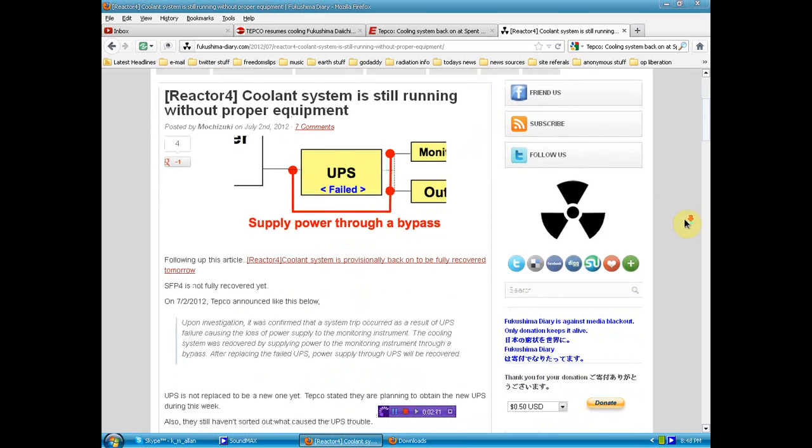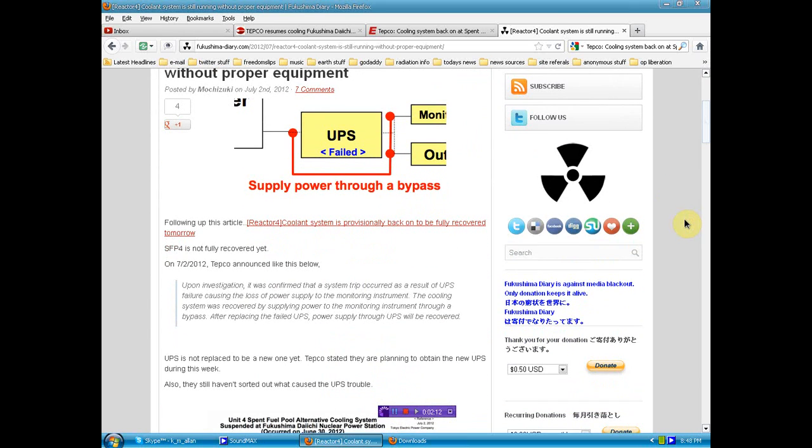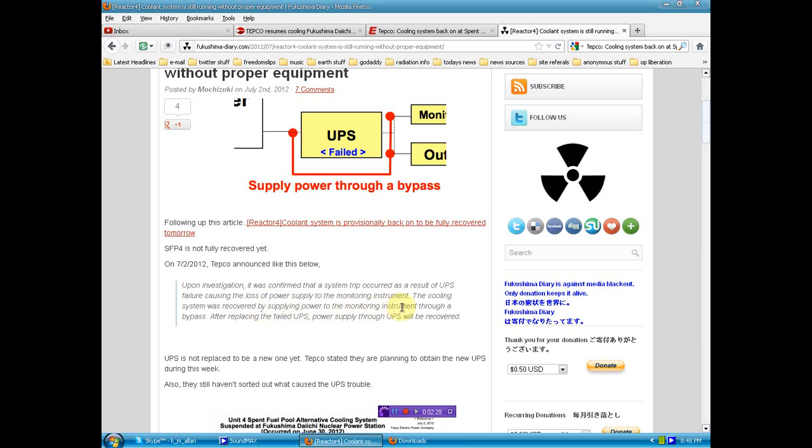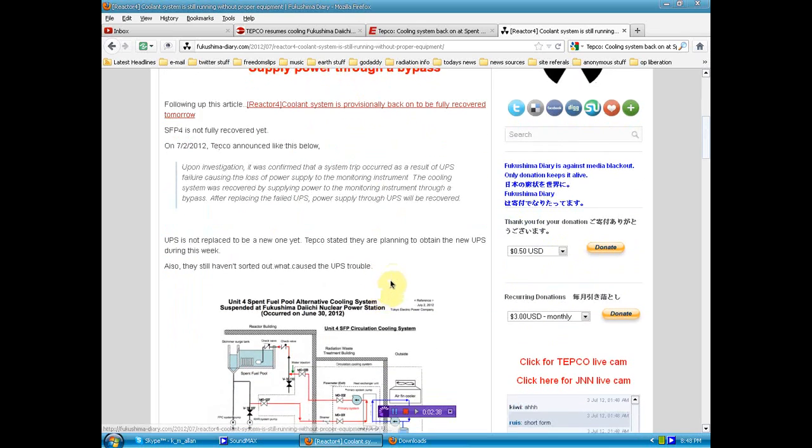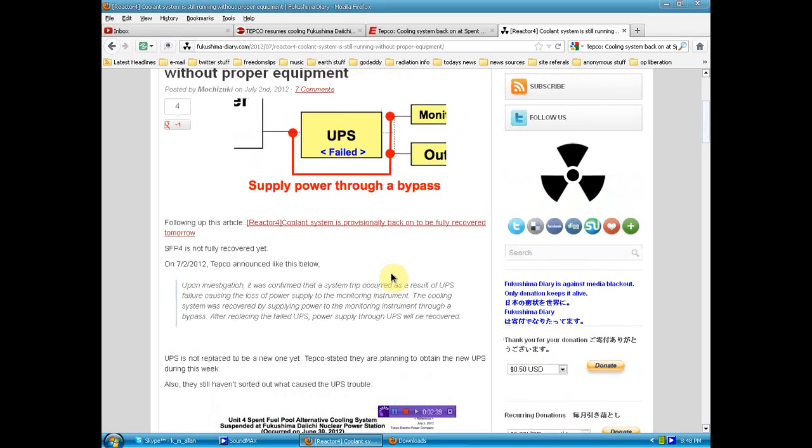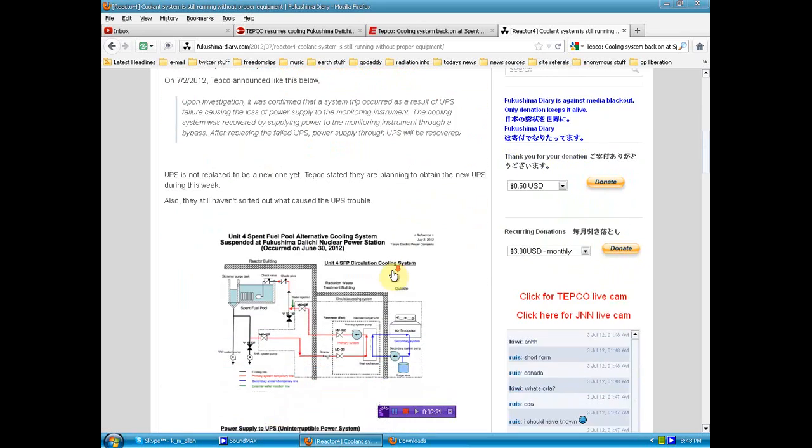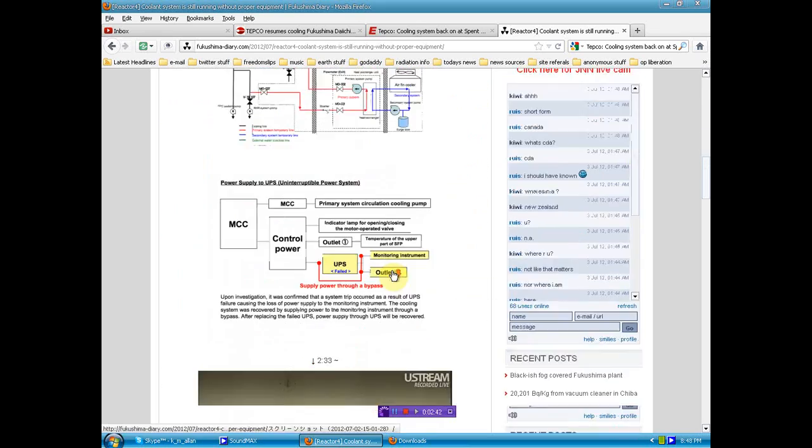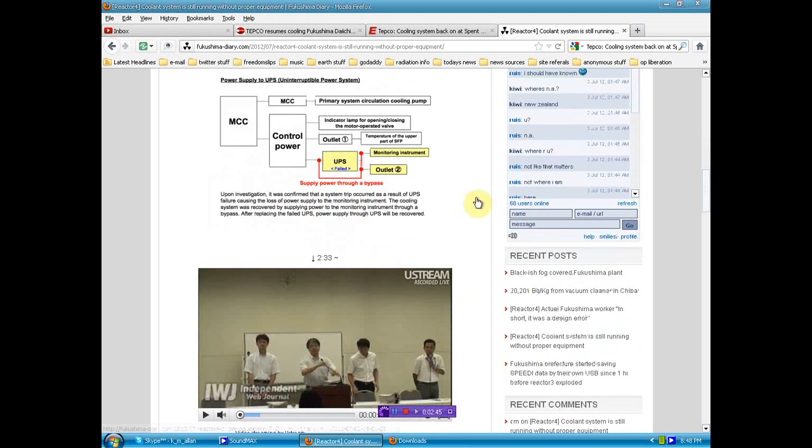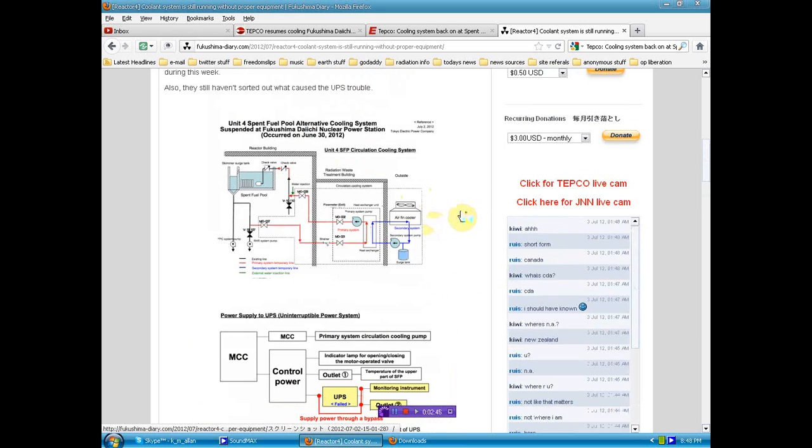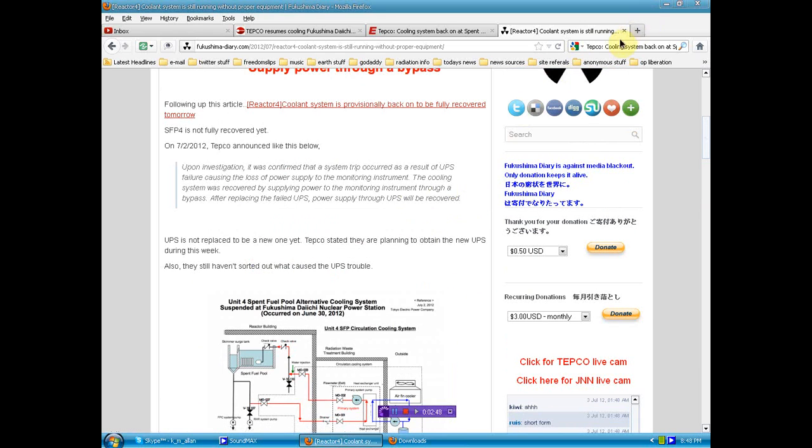Fukushima Diary backs up the story that upon investigation it was confirmed that this system trip occurred as a result of the UPS failure causing loss of power supply to the monitoring instrument. The cooling system was recovered by supplying power to the monitoring instrument through a bypass after replacing the failed UPS. The pumps have been restarted with a bypass, but it's still critical. There's still work to do and they don't have the parts on hand.